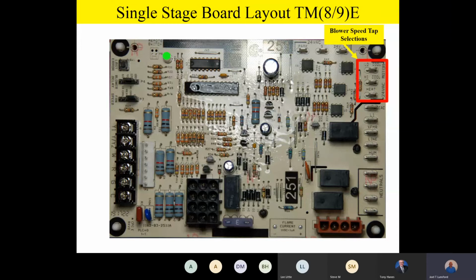And on that data plate, you're going to have a temperature rise range on the heating speed. So in other words, let's say, for instance, my temperature rise is 30 to 70 degrees. I want to select a heating speed tap on my motor to put me in a temperature range of about 50 degrees. So right about in the middle is where I normally try to put it for comfort.